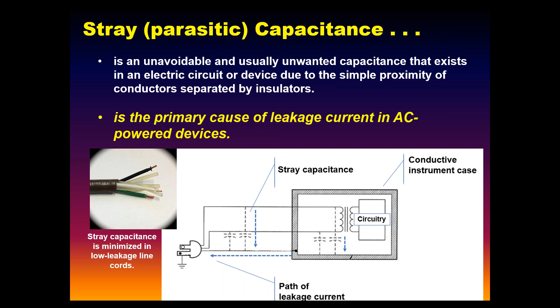So again, where I'm going here, these capacitors can actually be physical capacitors. You've probably had an occasion where measuring leakage on devices gives you way over 500 microamps. Any device with built-in line frequency filters has physical capacitors to ground inside.